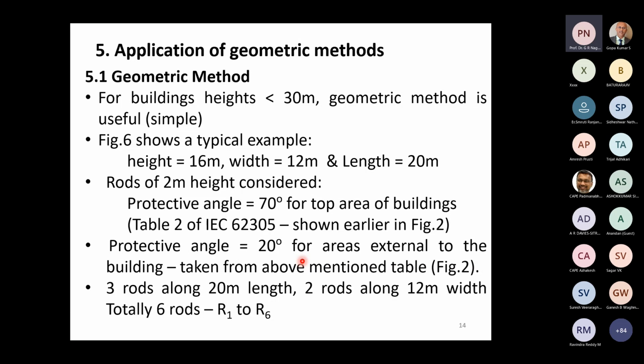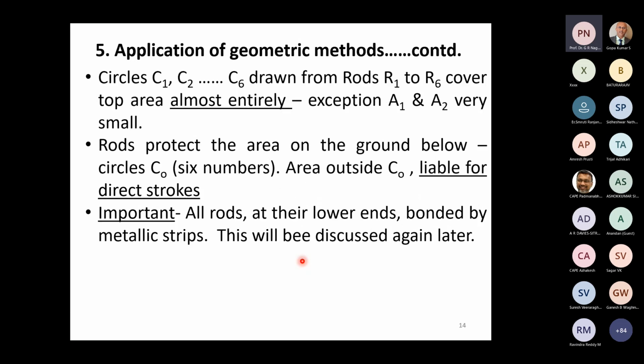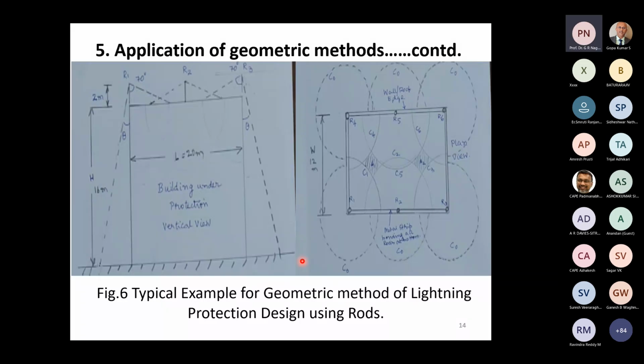Now, to give an example, I have a small figure here. A building which measures approximately 20 meters in length, height approximately 16 meters, all arbitrarily taken. On top of this, I would like to provide a Franklin rod, a lightning rod, approximately 2 meters in height. So how do I design the number of Franklin rods and their locations? The first thing I must always note is that the sharper the point, the more attractive it is for the lightning to come and strike. Therefore, the first thing will be to have a rod at the corners and along the edges, this corner and this corner. So where to put them along the edges? Now, I will put this rod here, 2 meters in height.